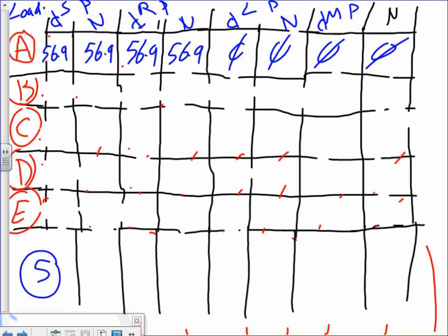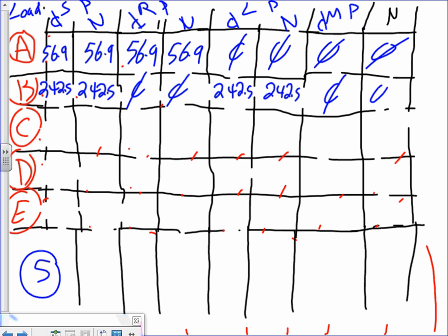Next, lighting panel. The lighting where B was lighting. What was the lighting? 24.25, 24.25. They are running at 120. Do they need a neutral? Yes, 120. Can you get 120 without neutral? Typically, no. You can get anything you want if you have a transformer, but typically in a building, if you see 120, you're on neutral, right? So because of the lighting and receptacles, remember, you always assume the same phase load will be for the neutral, because they need a neutral. So what's the number here? 24.25. Can it be seen by the receptacle panel? No. How about the lighting panel? 24.25. How about here? 0, 0.